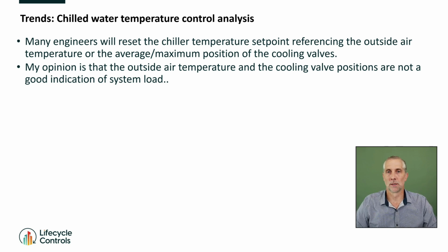So the example I want to talk through here is, in Australia, it's very common for BMS companies to reset the chill water temperature set point on cooling valve positions. And the idea here is that if the air handling unit and fan coil and chill beam cooling valves are all fully open, it means there's a high demand. It's probably hot outside. The building is very occupied. We're in full cooling. If the cooling valves are fully open, then we need lots of chilled water, lots of cooling. So the idea is if all the chilled water valves are mostly open, then we reset the chill water temperature set point down to 6 degrees Celsius, the design, and we give them full cooling.